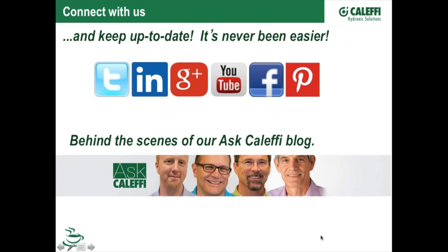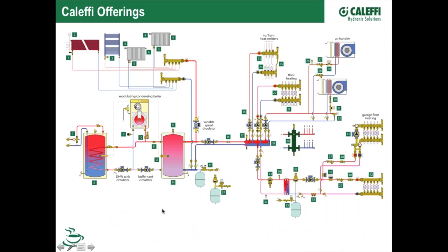Yeah, sure. We have a couple. I don't know if you can get back to your slides, but the schematics of the near boiler piping. In one schematic, it showed the pump pumping away from the boiler. On another schematic, showing the pump pumping into the boiler. Why would one want to pump away from the boiler versus pumping in, and vice versa?